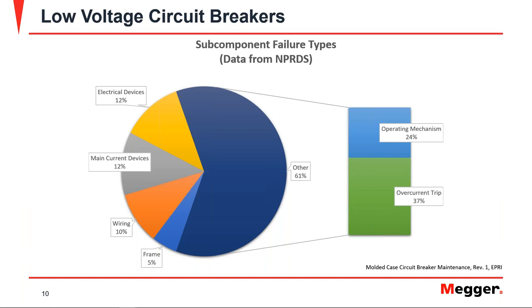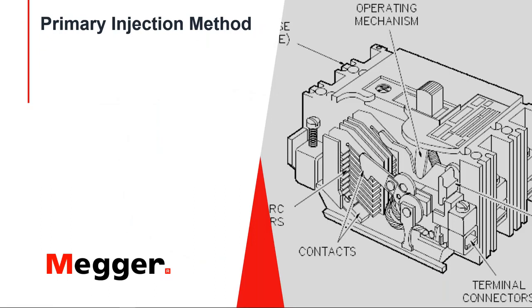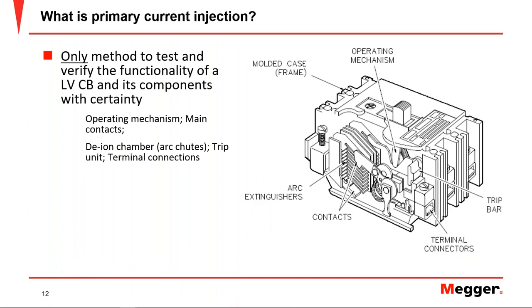So what do we use for the measurements? As I mentioned before, on low voltage circuit breakers, we use primary injection. So what is primary injection? I already mentioned it is the only method that we can use to test and verify the functionality of this type of breaker, as with this technique we'll be able to test all the elements of the circuit breaker: the operating mechanism, the main contacts, the arc chutes or the deion chamber to extinguish the arc, the trip unit, and the terminal connections. So everything is involved while we perform this type of test, primary injection.